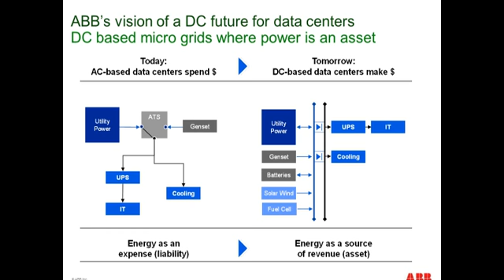While there may be times during a typical compute day with lower demand but greater on-site generation capacity, you'd want to transfer that excess capacity back to the utility via a smart grid. Marrying that microgrid structure on your property with the utility's smart grid off your property will allow the data center owner to sell back power, turning their power consumption into an asset. Tomorrow's data centers will be more agile and flexible than today when it comes to power.